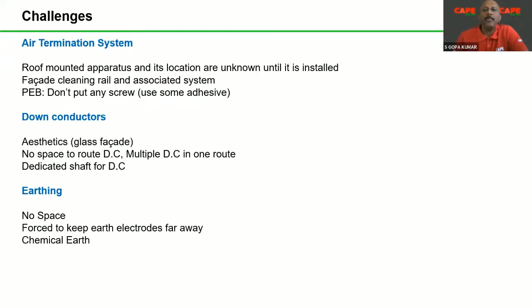The second challenge which we always face is the down conductor. Down conductor in large multi-storied buildings, if we say that down conductor has to be outside the building, then the first answer is no, no, no. That part of the building there is glass facade, this part of the building glass facade, so it will affect the aesthetics. You cannot do that.